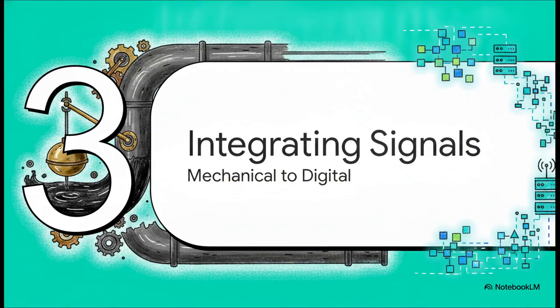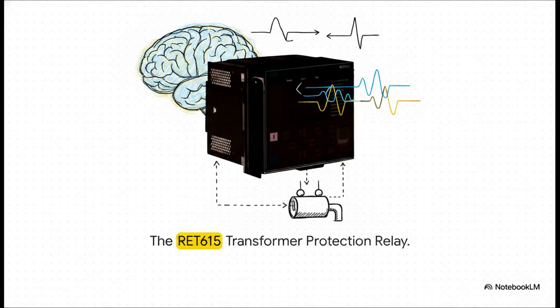Section 3. Integrating the signals from mechanical to digital. Now, what's really interesting here is figuring out how we get a mechanical float dropping in a pipe of oil to actually talk to a modern high-speed digital network. Enter the digital brain, the RET615 Transformer Protection and Control Relay. This is the unit watching the transformer 24/7. We already know it does an amazing job analyzing voltages and currents, but it also has to act as the central hub to interpret those physical, mechanical warnings coming from the Buchholz relay.